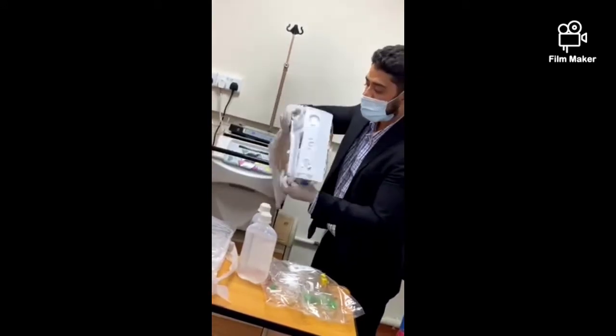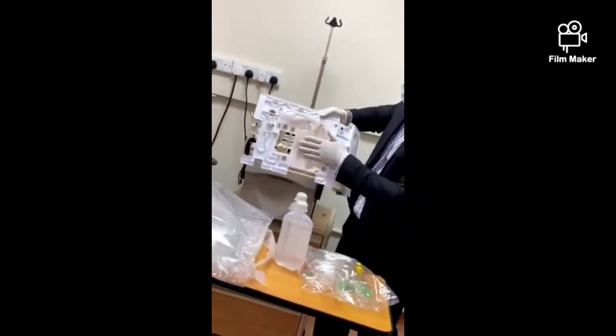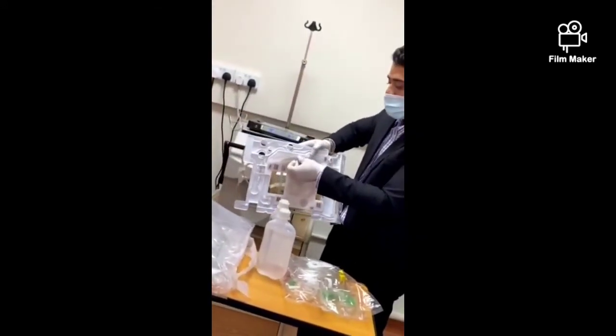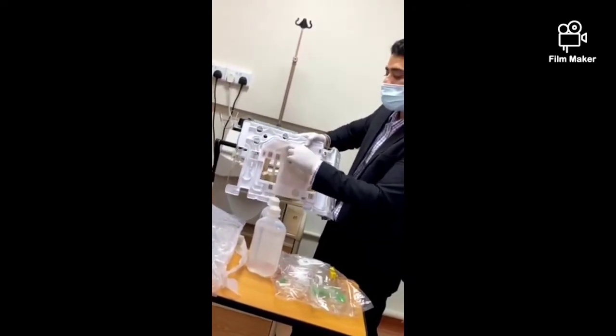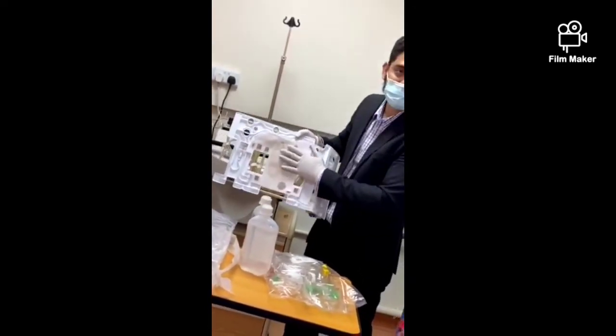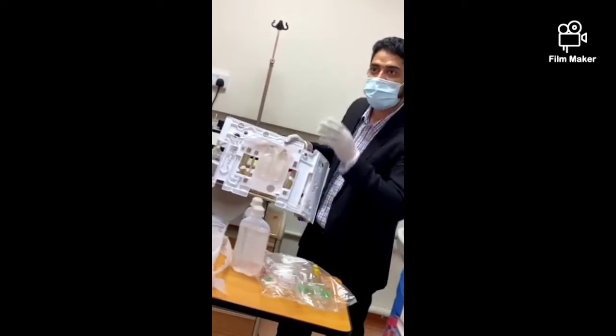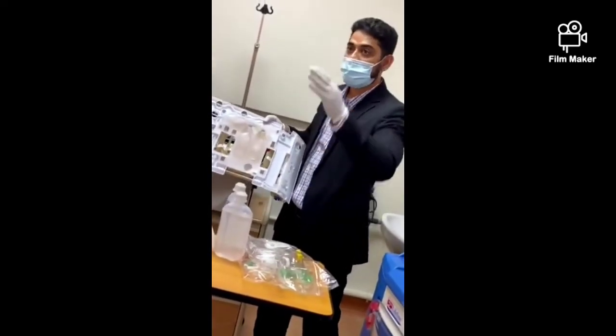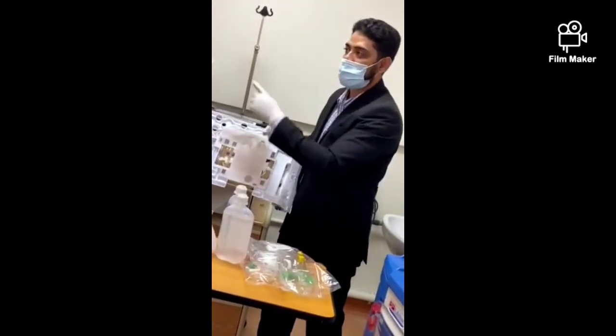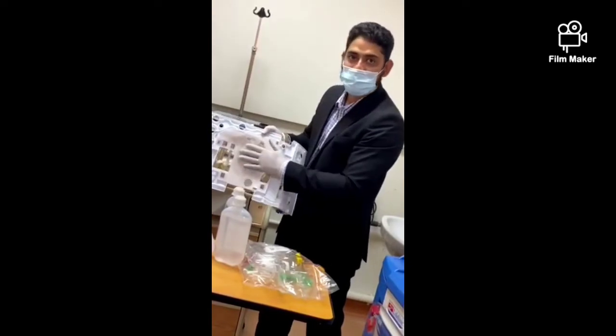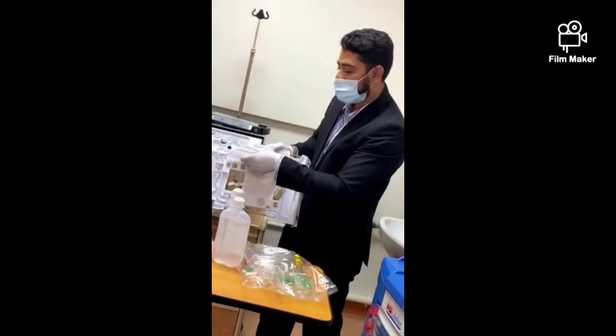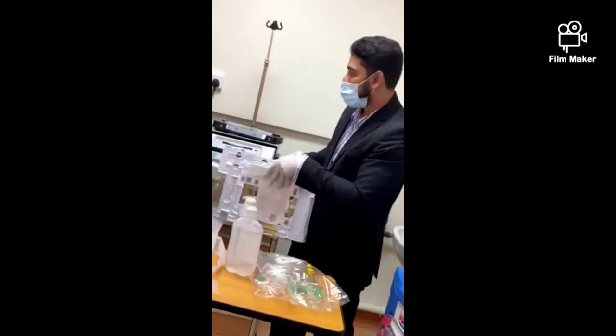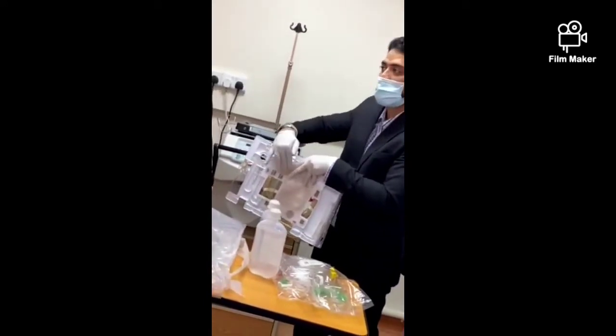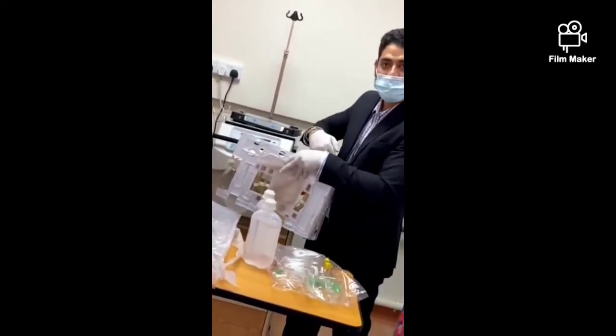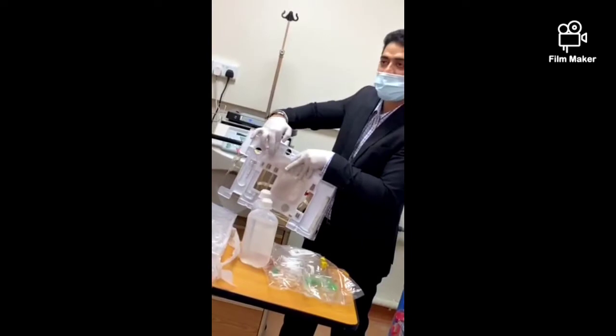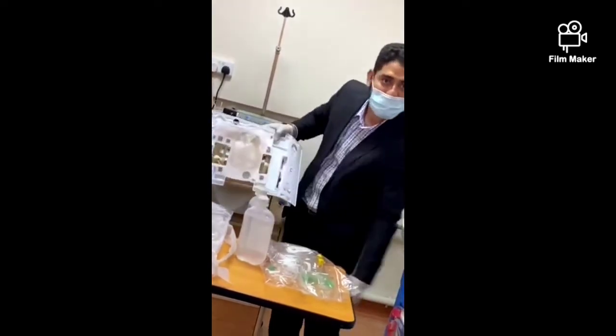Okay, and next, at the back side, we have the 2 bags. You see, 1 bag and 2 bags. So what is this name? This name is balance chamber. What do you mean by balance chamber? Balance chamber is inside this machine also, we have balance chamber inside. But in every kit we have 1 balance chamber. Of these 2 bags, 1 bag is for the pure dialysate. The dialysate will come here first and will go to the filter. And after the filter, it will come and collect in another bag before going to the drain.